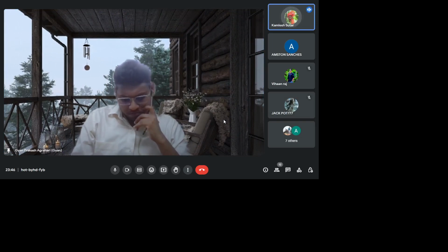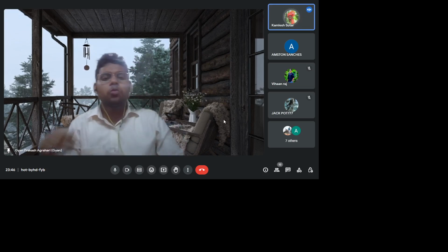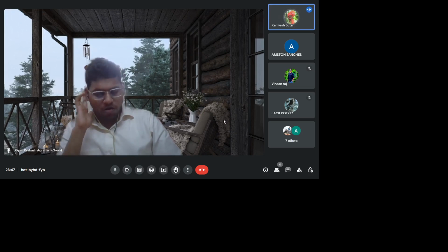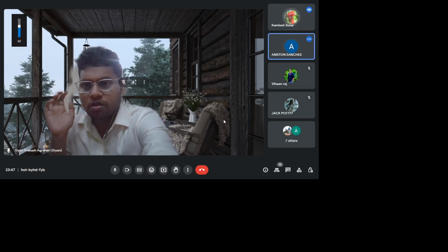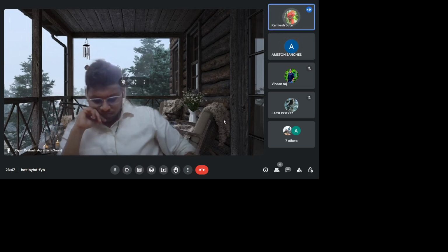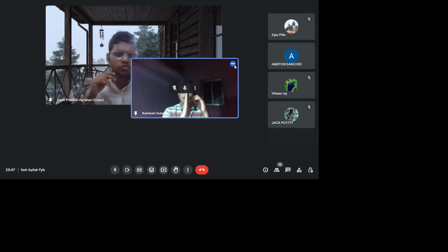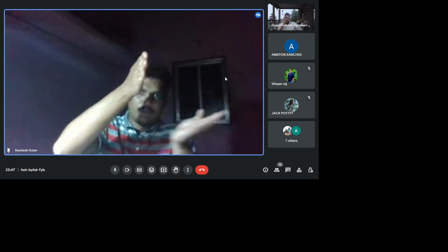No worries. In case of a needle valve, you have a conical shaped valve seat over which the needle goes, which is restricting the flow. As you open the handle, the needle will go up and the cavity allows the water to flow from the bottom to the outward discharge side. In case of a gate valve, it's a continuous section, and there is one barrier, which is called the gate. As you rotate the handle, this gate will go upward and the flow will continue.